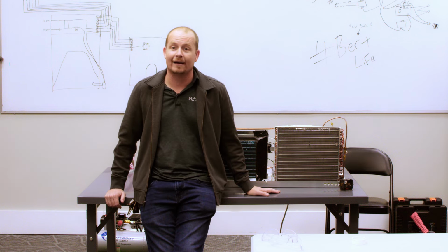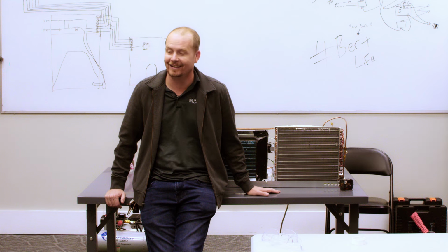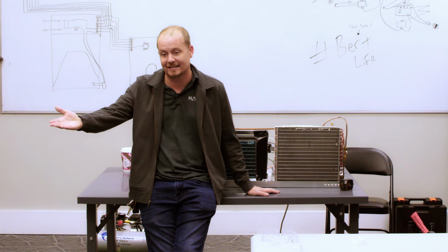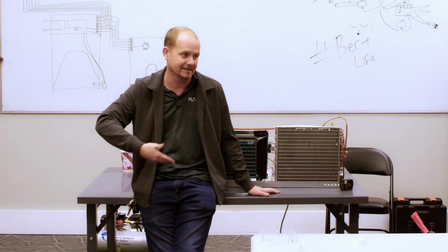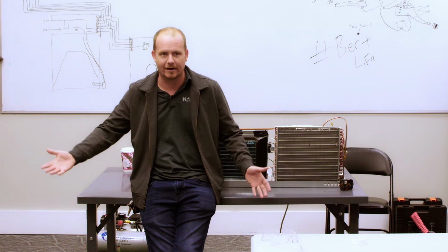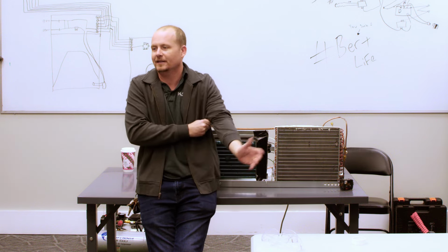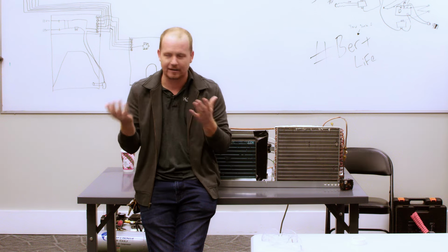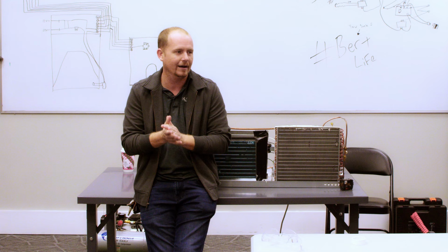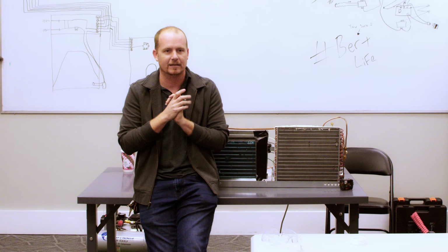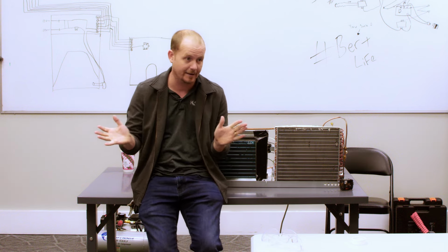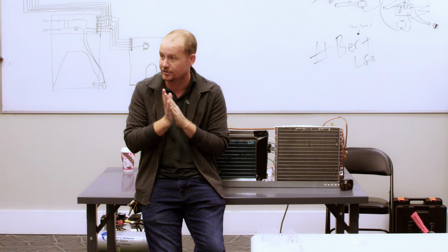And you do it only after what? You realize the line set's over 100 feet? Well, the line set is abnormally long, correct? And then you're weighing it in based on your estimated length of line set and all that sort of thing. These are all the right answers. You're giving a lot of good answers here. It's run a while, you're weighing it in, you're doing that based on estimated line set length, because all of them have information on how to do that within the installation instructions.